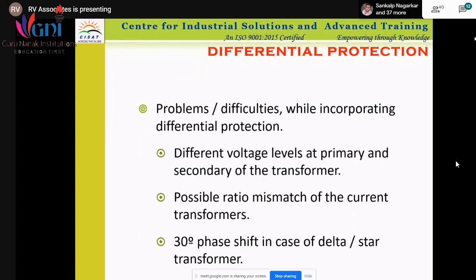So last one, please note this, there is a 30-degree phase shift in case of delta or star transformer. So that's why I told that when winding is a delta, CT to be star. When winding is star, CT used to be a delta one, which will give you the 30-degree phase shift.